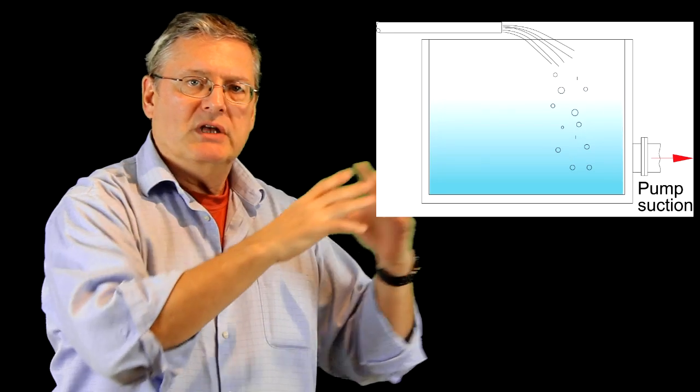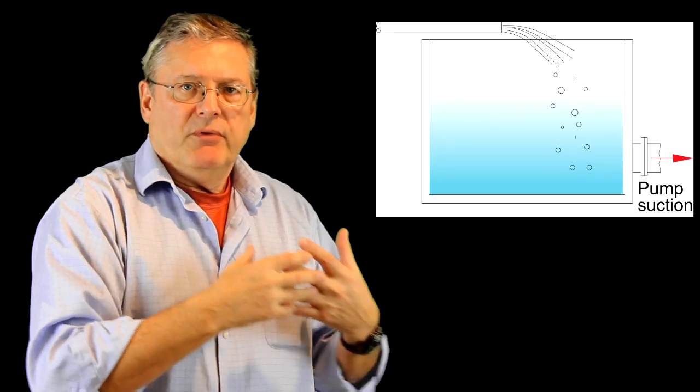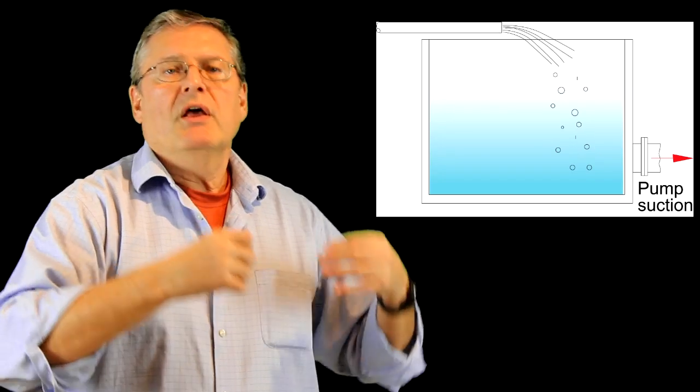If you bring them in more or less willy-nilly, if there's a high rate of flow, they're going to disturb the surface and cause a lot of air to be entrained downward into the pump. So try to bring them in vertically, nice and smooth, under the fluid level, and as far away from the suction as possible so as not to affect the streamlines going into the pump.